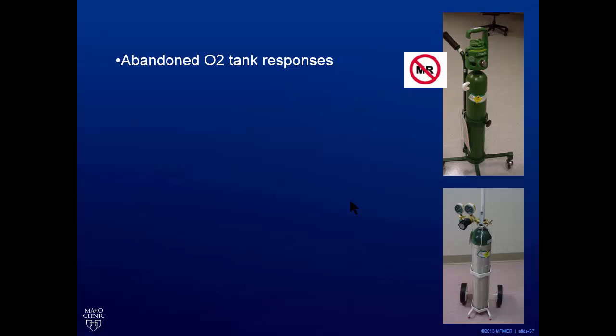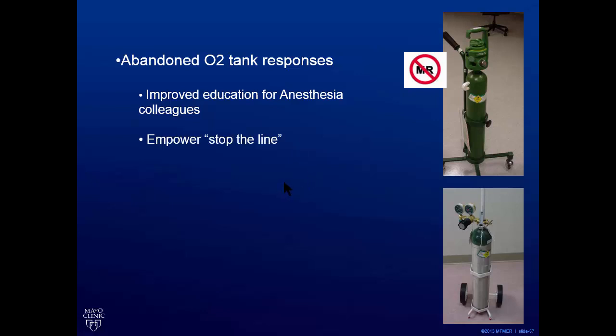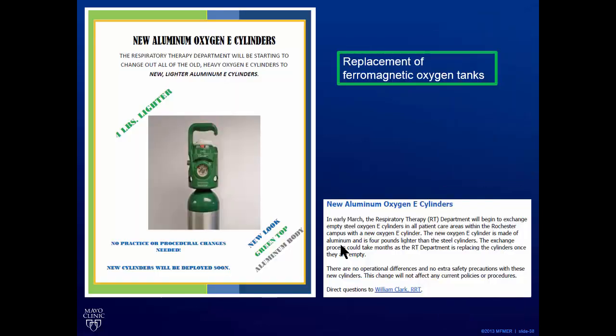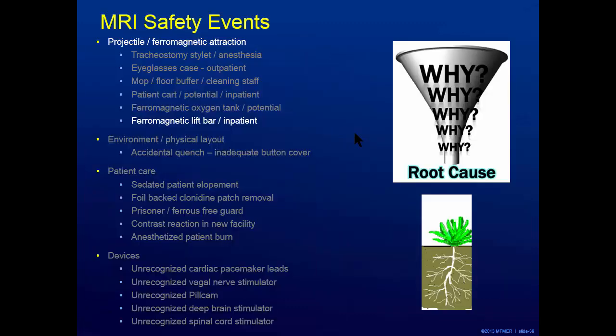We used this to our advantage. We needed to improve our education of anesthesia colleagues who left the tank there, and we let it be known that anyone who sees such a thing should stop the line. We used this as our way to get our foot in the door to say we need to get ferromagnetic oxygen tanks out of our shop at Mayo Clinic. We got administration's ear and were able to get this through. The kicker is the carts need adapting — aluminum tanks are three-eighths of an inch different in diameter — but you can sell it on the ergonomic benefits since aluminum tanks are much lighter. Nursing loved it, and that helped us get buy-in. By and large, we've gotten the ferromagnetic tanks out of our place.